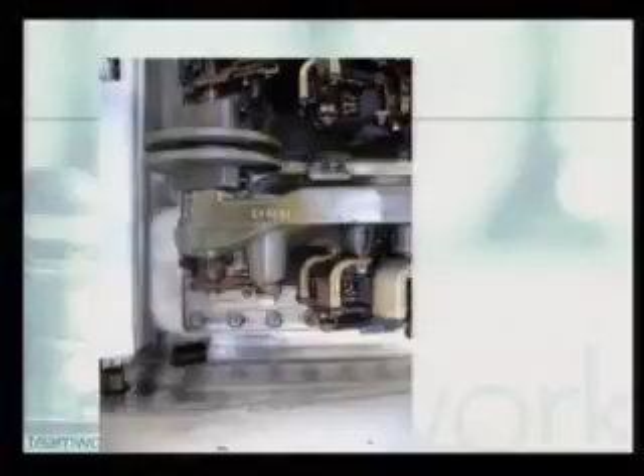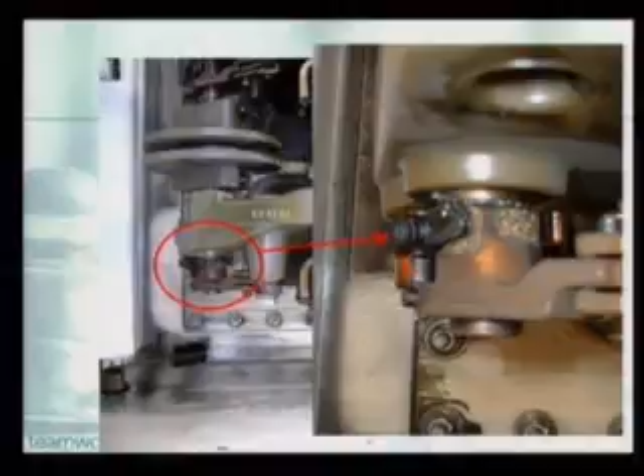But in here, on that corner, I'll focus on that, there's actually a problem. As you can see here, it's deteriorating. There's some problems there where it's actually a source of a high point or a hot spot, we call a hot spot. And if you look at that even closer, the contacts are no longer making good contacts, it's carbonized. Actually, I have that sample here. Don't touch it with your white shirt. What we're looking for in electric systems is basically to make sure that we have good solid contacts. So there's just a closer picture of that. And the part that failed, as you can see, is completely carbonized and deteriorated from the high heat.